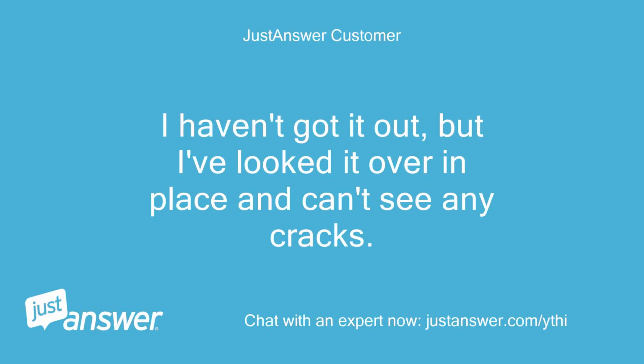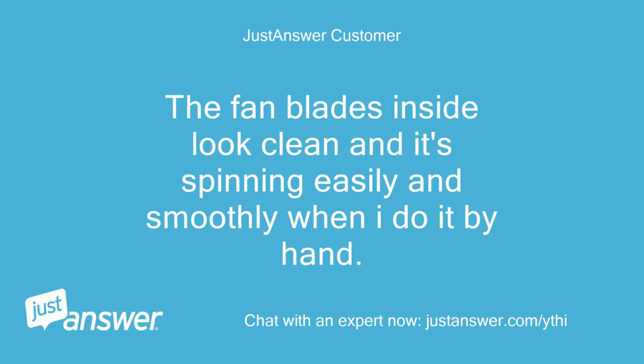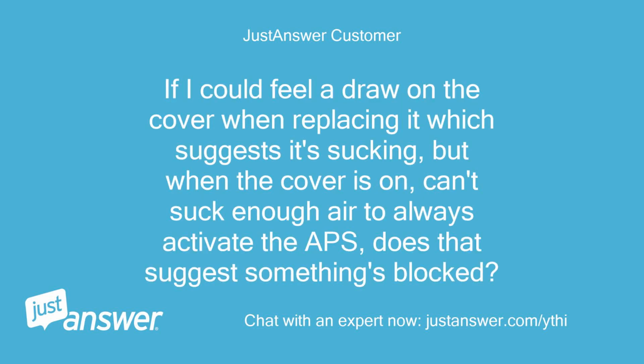I haven't got it out, but I've looked it over in place and can't see any cracks. The fan blades inside look clean and it's spinning easily and smoothly when I do it by hand. I can feel a draw on the cover when replacing it, which suggests it's sucking, but when the cover is on, it can't suck enough air to always activate the APS. Does that suggest something's blocked?